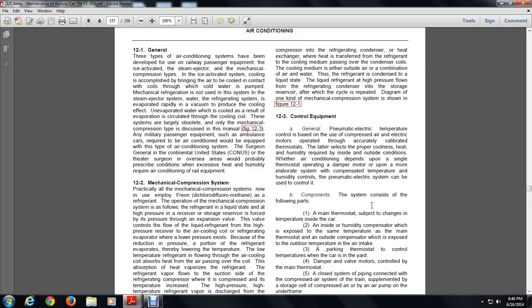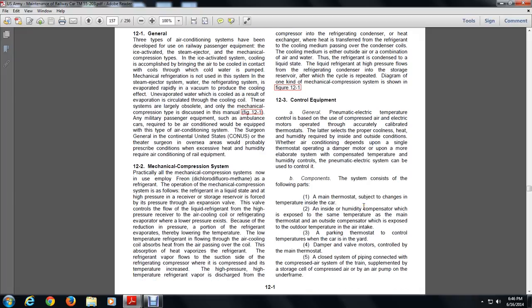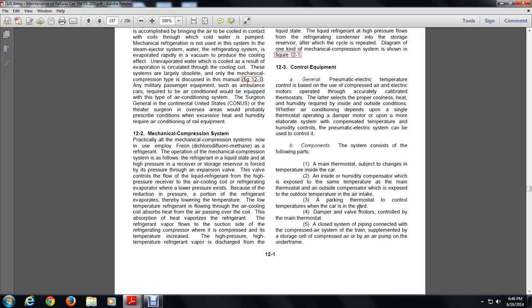The components of the control system consist of the following parts: (1) The main thermostat, subject to the change of temperature inside the car. (2) The inside humidity compensator, exposed to the same temperature as the main thermostat, and an outside compensator exposed to the outdoor temperature at the air intake. (3) The parking thermostat to control car temperatures when parked. (4) The damper and valve controlled by the main thermostat. (5) The enclosed piping system connected to the compressed air system of the train, supplemented by storage or an air pump on the underframe.